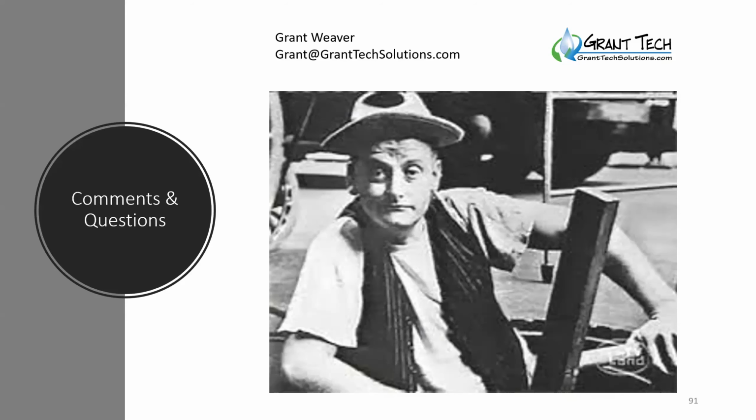Not only that, but you answered the next question I had flagged, which was, is a dedicated upfront anaerobic zone also an option for biophosphorus removal in SBR systems? They are, and there's a technology that has them. I've only worked with one. I've worked with it remotely, and they had a real problem driving it septic enough. And we worked with the manufacturer on that, who was super helpful.